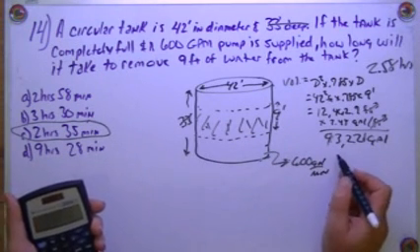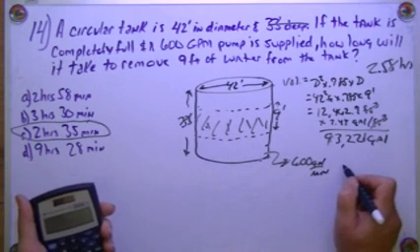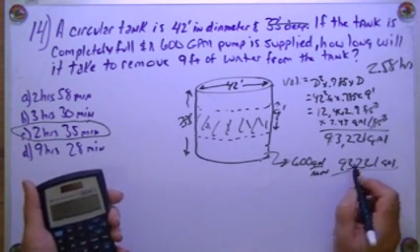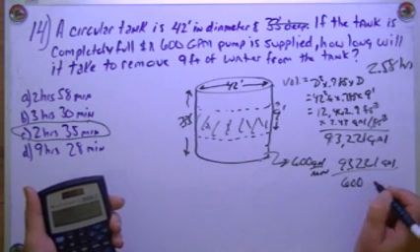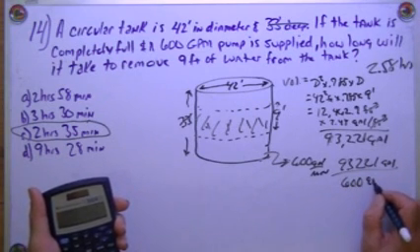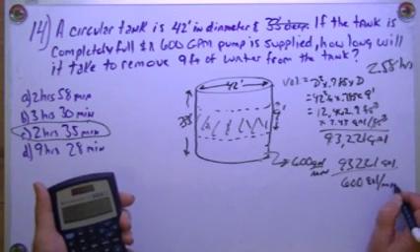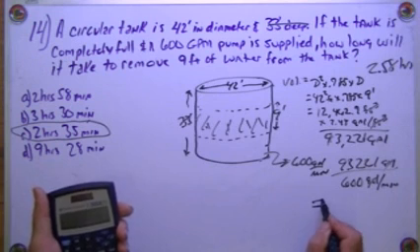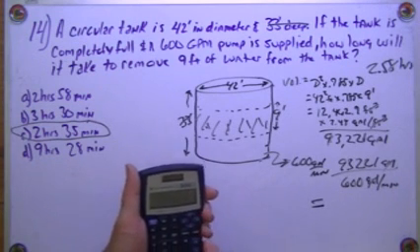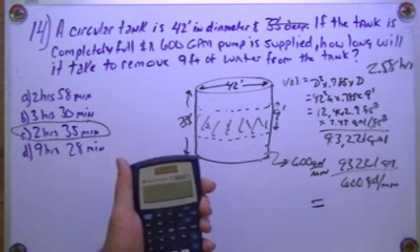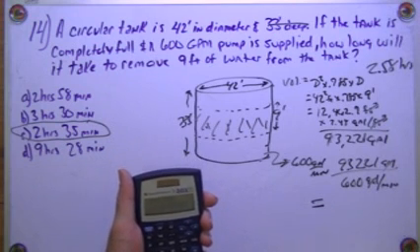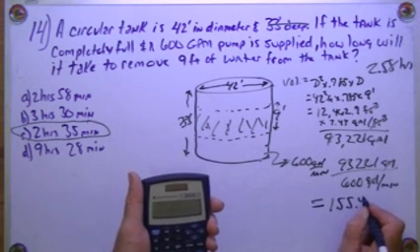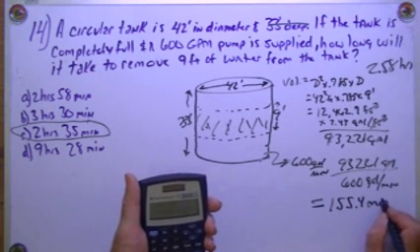But I want gallons per minute. So I'm going to take 93,221 gallons divided by 600 gallons per minute. Gallons are going to cancel out, and I'm going to get minutes. So I'm just going to divide it by 600, and I'm going to get 155.36, 155.4 minutes.